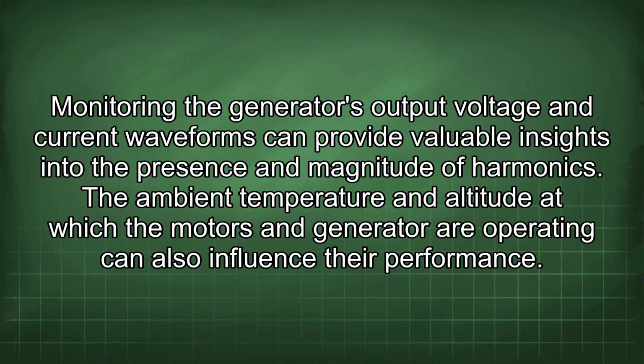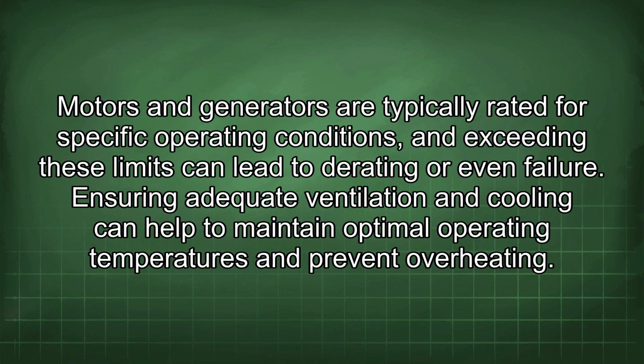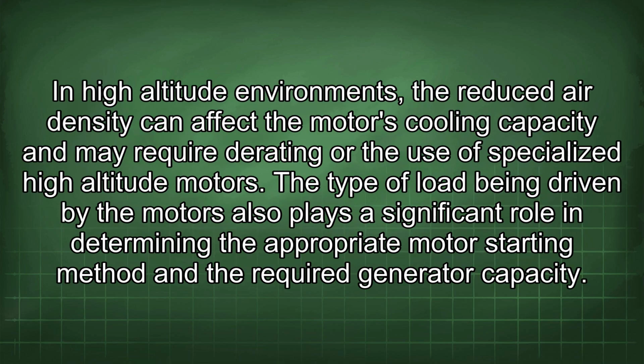The ambient temperature and altitude at which the motors and generator are operating can also influence their performance. Motors and generators are typically rated for specific operating conditions, and exceeding these limits can lead to derating or even failure. Ensuring adequate ventilation and cooling can help to maintain optimal operating temperatures and prevent overheating.